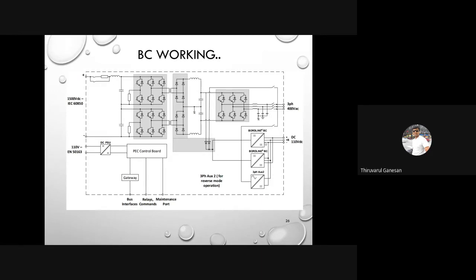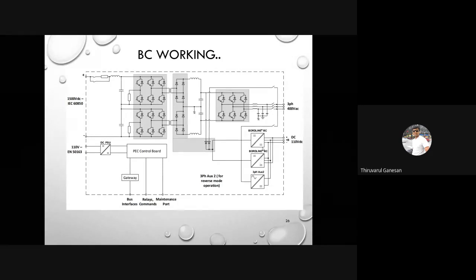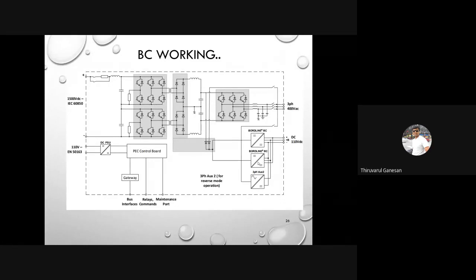In this case, I would say this charger is maybe 10 kilowatt, and this is 10 kilowatt. Put together, it is a 20 kilowatt system, and if the customer needs a single charger to charge the battery system, you will go for 25 kilowatt or 30 kilowatt based on the next available design. So it is a specific design for the customer. If one of the chargers fails, I don't want to lose all the auxiliary loads of my train. The other charger can charge the battery, and it will survive until the next station.